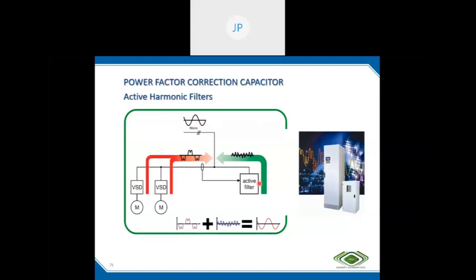What the active harmonic filter does is sense the nature of the spectrum, the magnitude, everything, and generate the harmonic components of this load current and inject them in the opposite direction. A mirror image will be generated and injected so that both harmonics are equal and opposite, and it will nullify them. Here, this is the distorted current, and we are injecting a mirror image of the harmonic content, and the result is a sine wave.